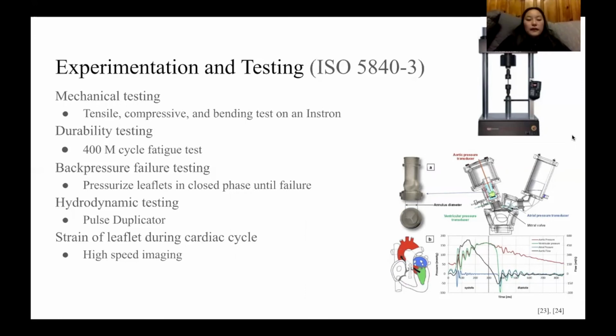The failure pressure of the valve could be found by pressurizing the leaflets in the closed phase during a back pressure failure test. Hydrodynamic testing could be done using a pulse duplicator to see how the replacement valve behaves in an environment similar to within the body. The strain of the leaflet during flow could also be seen using high-speed imaging, as performed in several other studies.